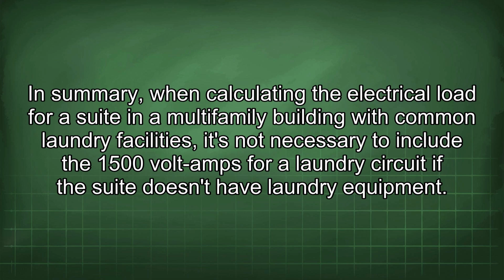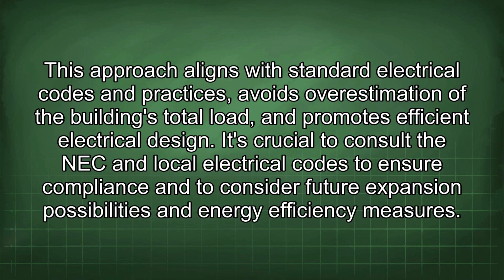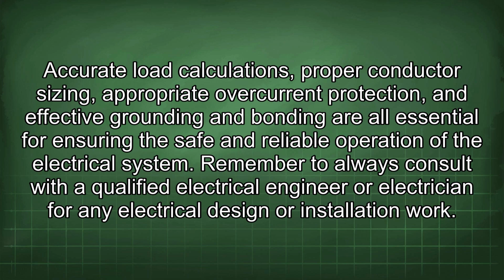In summary, when calculating the electrical load for a suite in a multifamily building with common laundry facilities, it's not necessary to include the 1500 volt amps for a laundry circuit if the suite doesn't have laundry equipment. This approach aligns with standard electrical codes and practices, avoids overestimation of the building's total load, and promotes efficient electrical design. It's crucial to consult the NEC and local electrical codes to ensure compliance and to consider future expansion possibilities and energy efficiency measures. Accurate load calculations, proper conductor sizing, appropriate overcurrent protection, and effective grounding and bonding are all essential for ensuring the safe and reliable operation of the electrical system.